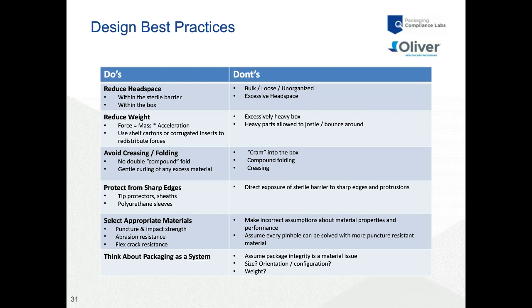And that also shows that seal strength is not always one pound, right? It's a big conversation point in industry today: how do we move away from this rule of thumb of one pound? And we can see that sometimes we need more than a pound. We have heavy parts inside a tray to contain that and prevent the seals from popping open.